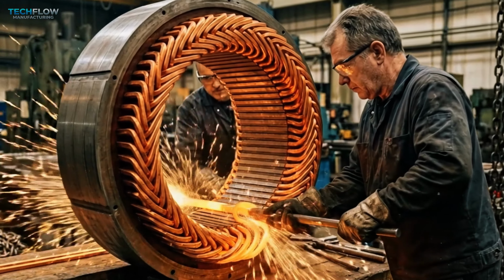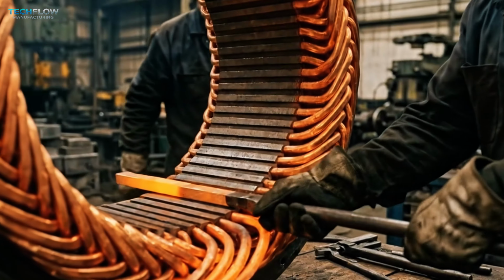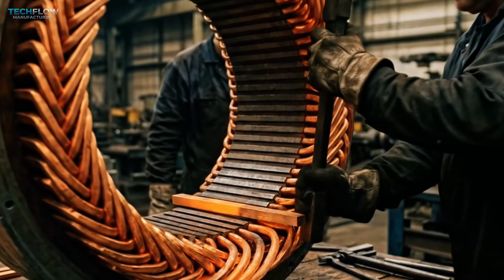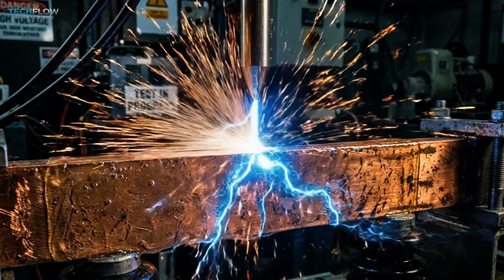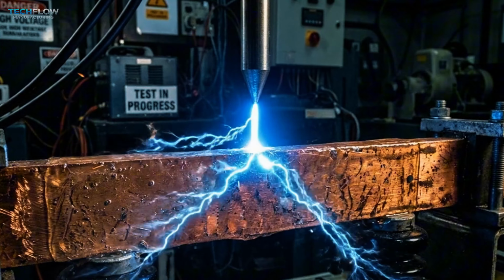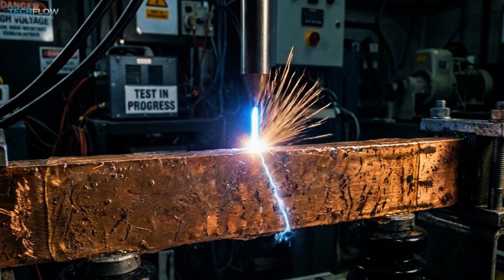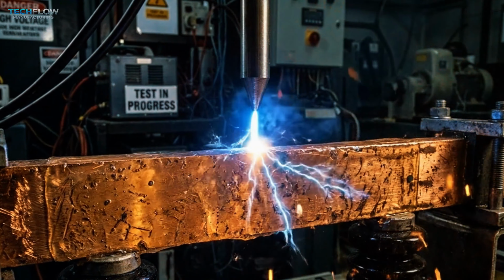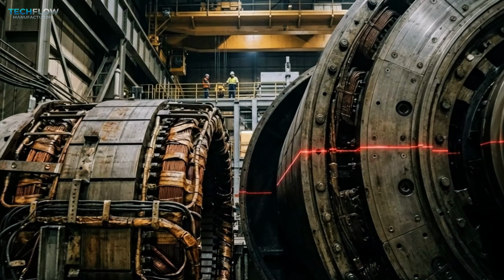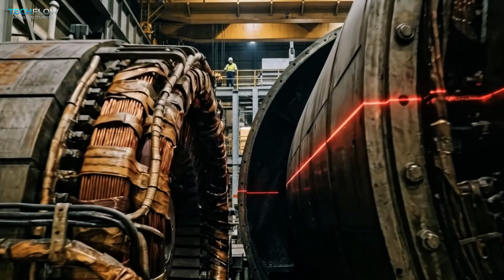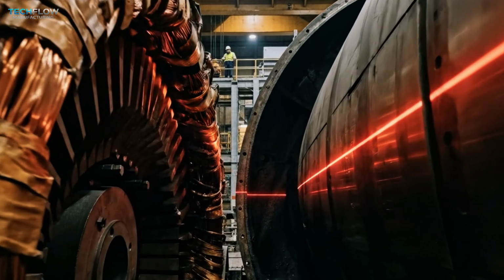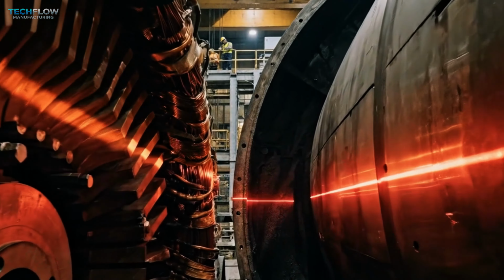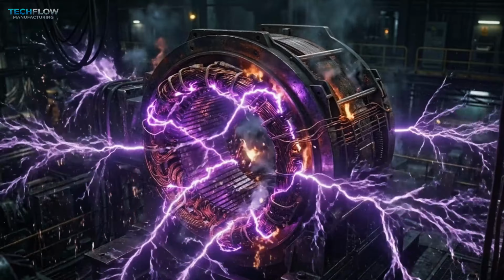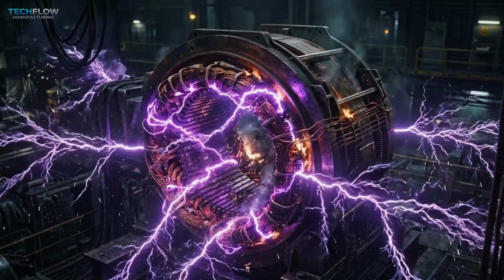The stator frame, a colossal ring of steel, is being wound with thousands of kilometers of high-purity copper. Each copper bar is insulated with advanced resin composites to withstand potential differences of over 20,000 volts. Precision is paramount. The air gap between the rotor and stator is just a few millimeters across a 5-meter diameter. Any contact at full speed would result in an immediate electromagnetic explosion and total system failure.